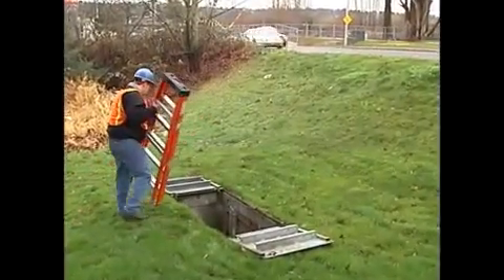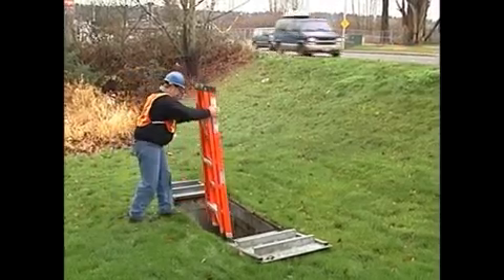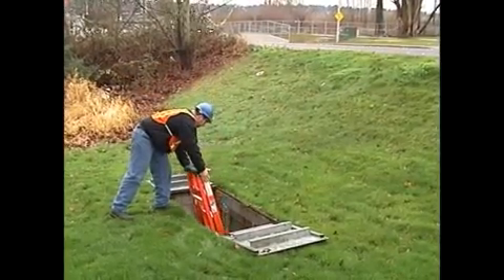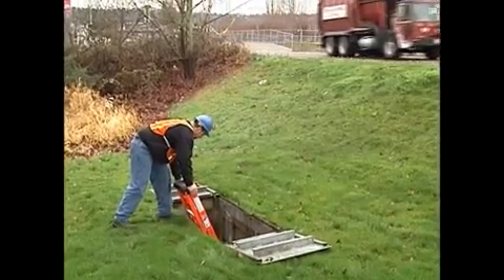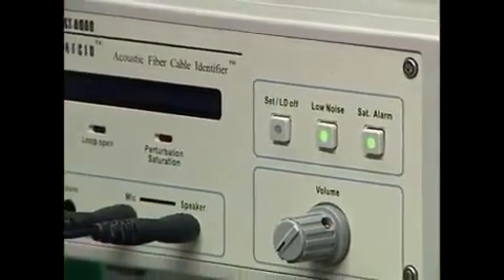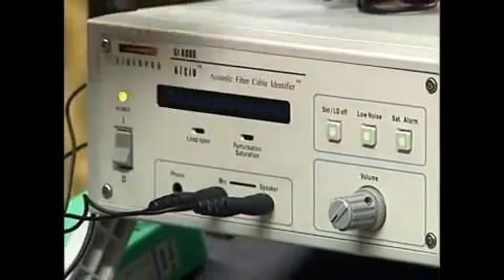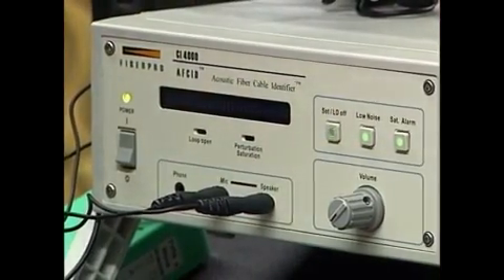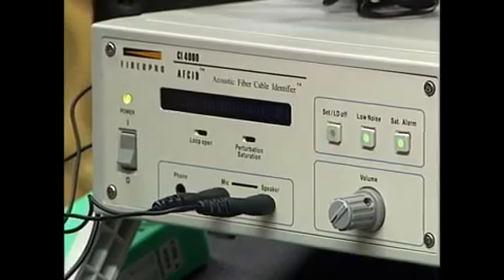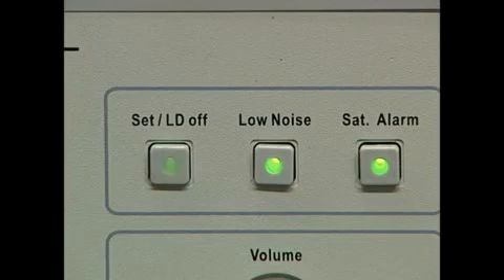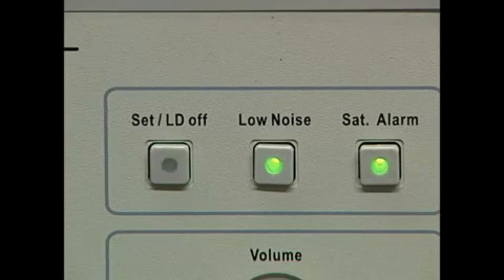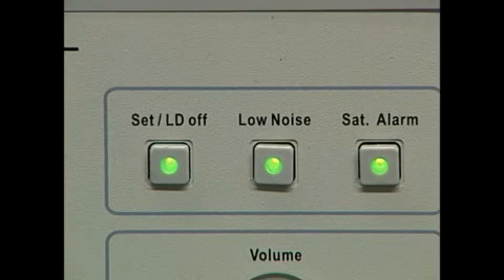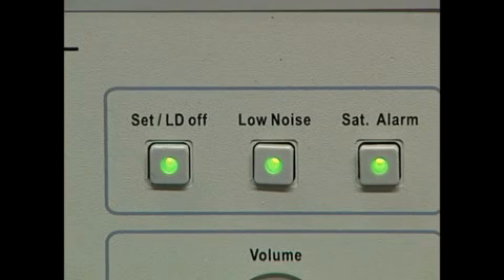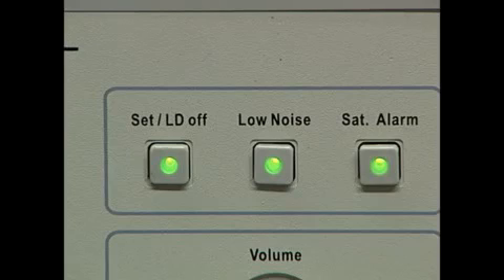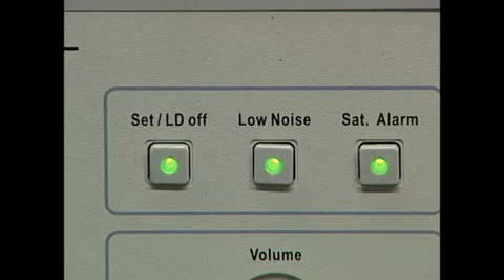The field technician accesses the cables to be tested. Be sure to follow all local and national safety codes when working in confined spaces. When the cables have been accessed for testing, the central office technician presses the Set LD Off button to start the instrument's laser. The LED and the push button will flash for a few seconds while the instrument calibrates and initializes the interferometer. During this time, the field technician must not disturb the cables. When the calibration is complete, the Set LD Off button will remain illuminated and the instrument is ready for testing.